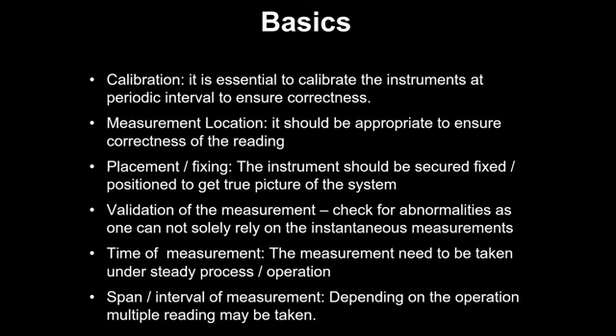Then basically comes how many readings we should take. Sometimes, when the criticality is higher, especially for flow measurements, the reading is very critical and shows some variations. Say we connect the flow meter and the flow is varying from 200 to 220 meter cube. It can happen because of many parameters. We will not discuss that now, because that would be another topic for a presentation, but it can happen. So what do we do under such conditions?